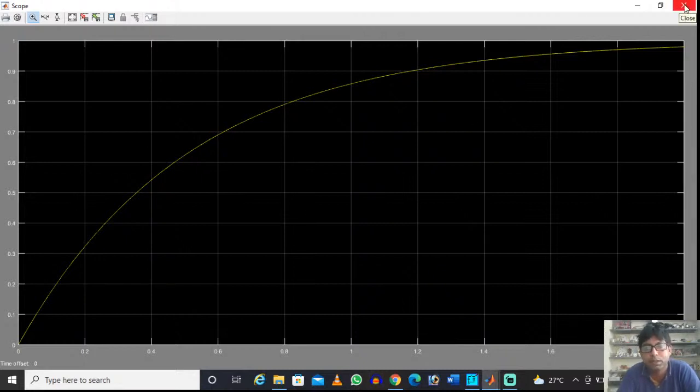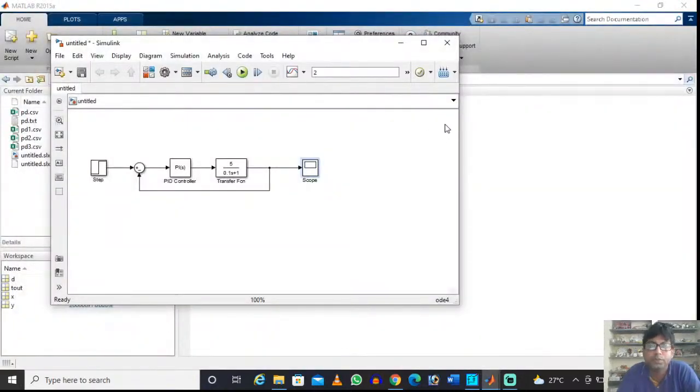So I hope this example will be useful for you to estimate the system transfer function from the time domain data, and by considering the design requirement and the operating requirement, how to tune the PI. Rather than going the trial and error route, there are a lot of methods, like Cohen-Coon, and Ziegler-Nichols, all these things we studied, but in industry you need to do it very quickly. So using this technique, I have tuned a lot of systems perfectly. I have shared my experience with you.